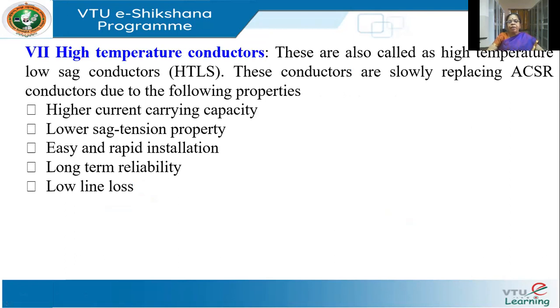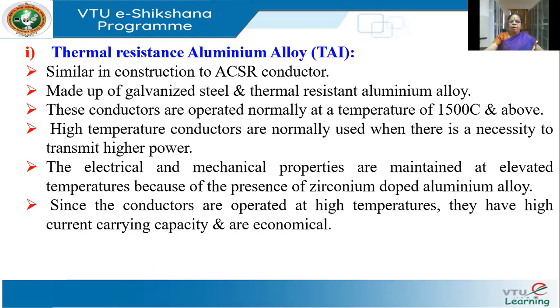Next, we have what are called HTLS — high temperature conductors. These have very low sag, and slowly they are replacing ACSR conductors because of their very high current carrying capacity, low sag, good tension properties (meaning even if tension is high, the sag is low), easy installation, reliability, and low line losses. They are still expensive but are becoming a popular choice.